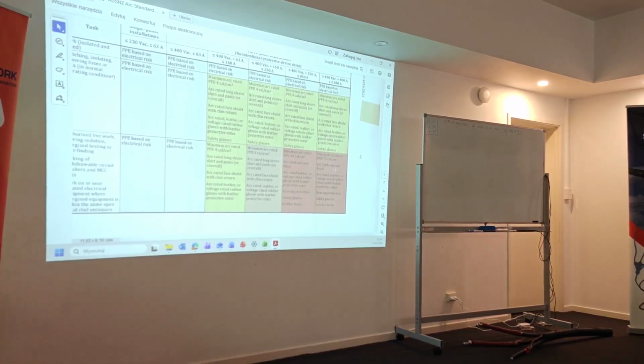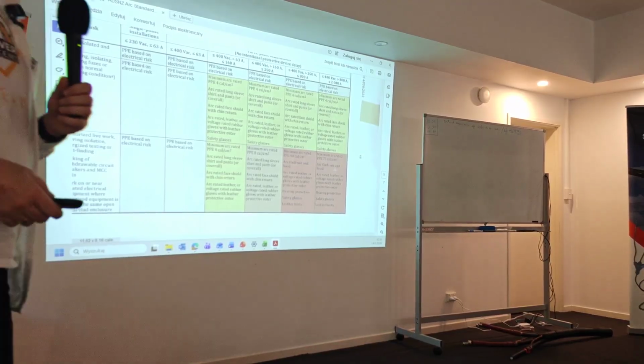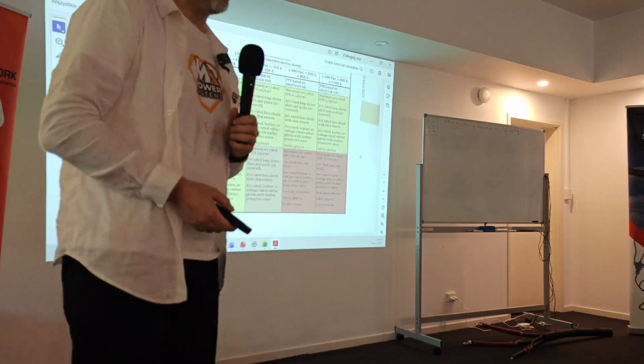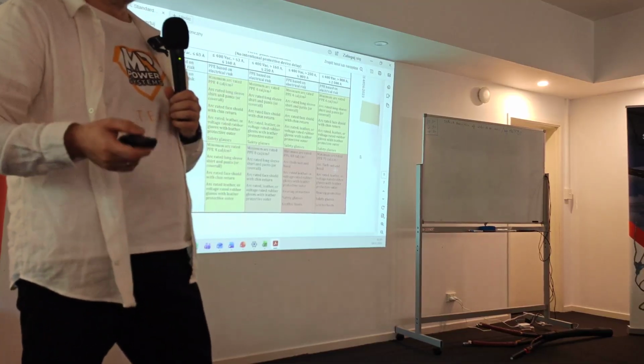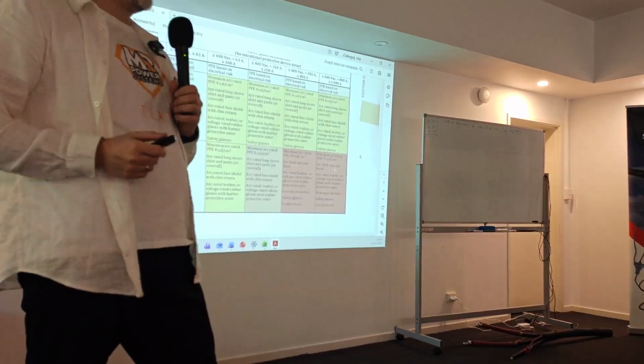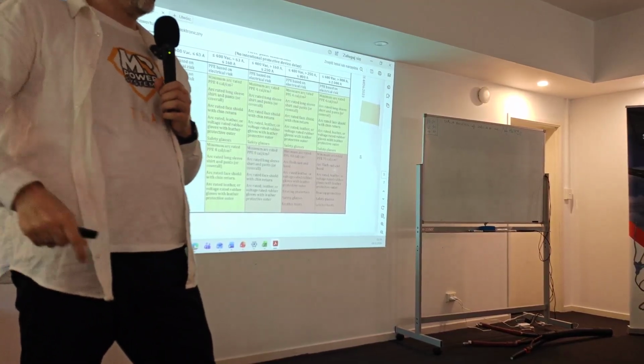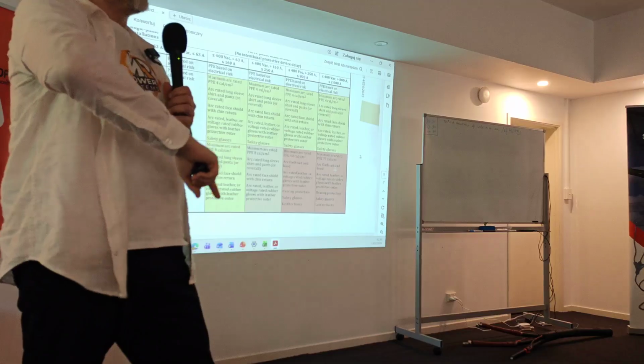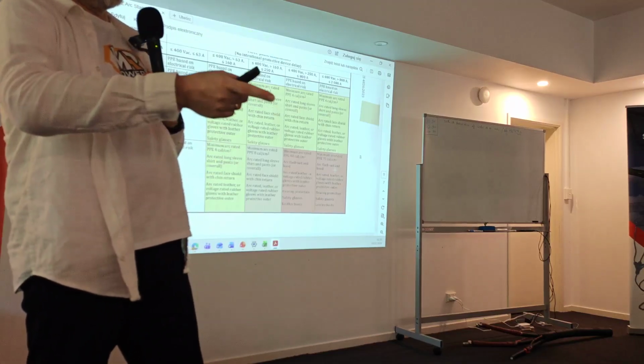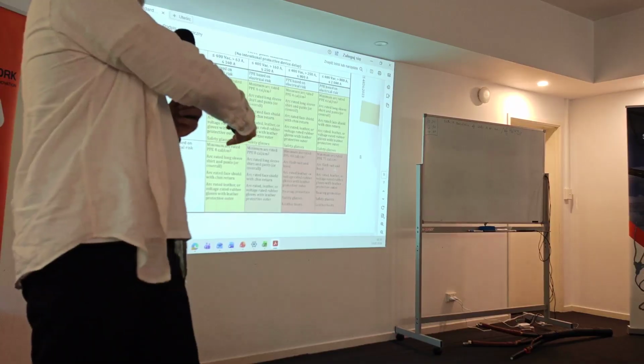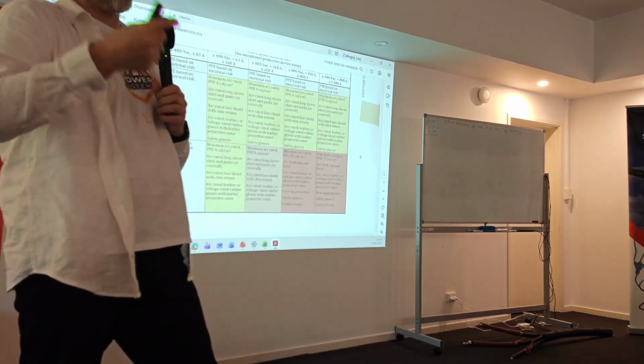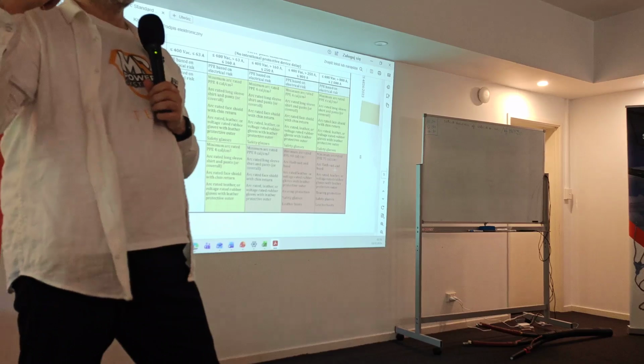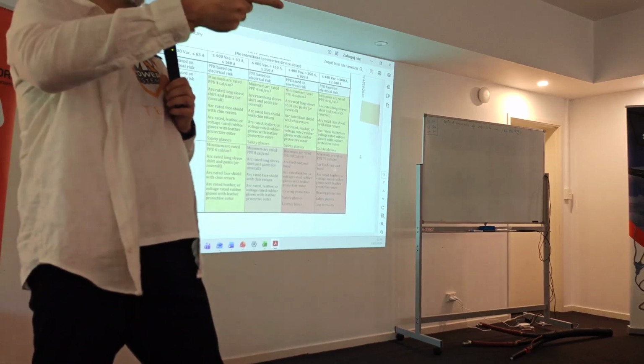I was going to ask you, how are arc flash calculations carried out on anything over 15 kV? Above? Yeah. So not with IEEE, because IEEE is up to 15 kV. If you want to go above 15 kV, on Monday I said there was a technical report from EPRI, Electric Power Research Institute in the US. They wrote this report, and based on it there are calculations done. You can use this by hand, of course, but some software, I think ETAP has it built in. SKM has something similar built in.